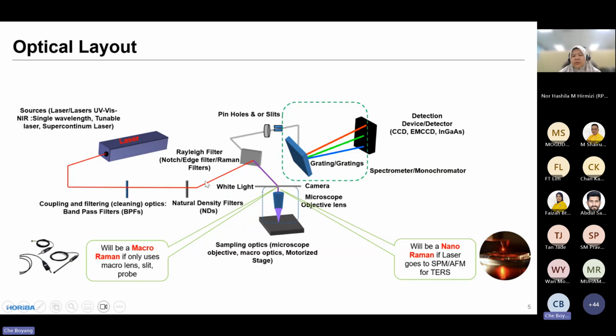After going through all the filters, the laser light will go to the Rayleigh filter, and it will first be reflected to the microscope part. When the light goes through the microscope and finally through the objective lens, it will reach the sample. This is your sample stage, and the light will interact with your sample. So you get all the scattering phenomena: Rayleigh scattering and Raman scattering. The scattering will go in all directions. A portion of the scattering will go back through the same optical path, through the objective lens and through the microscope.